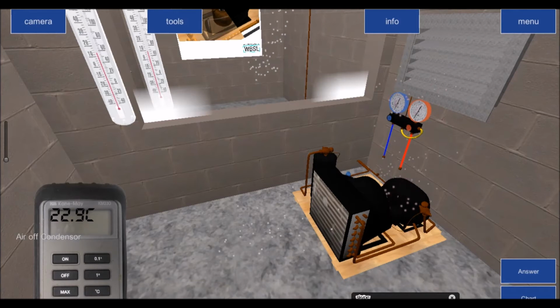Usually it's in the middle. Usually it's about 6 or 7 degrees. So my air off, if it's coming on at 20, should be coming off at 26 or 27 degrees. In our particular case, it's coming off at 22.9, which is about 3 degrees of a difference. Well, it's 2.9 degrees of a difference. So if anything, that's too small of a temperature difference. It should be a minimum of 5 degrees of a temperature difference. Anything less is too small.